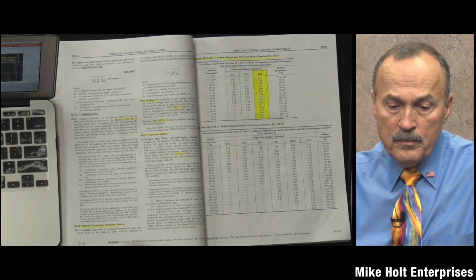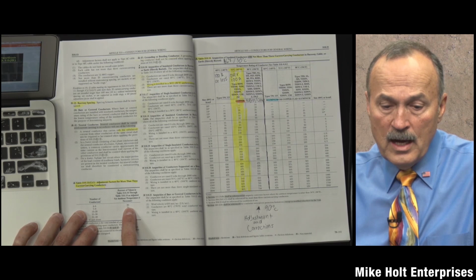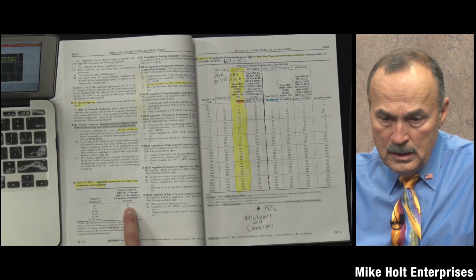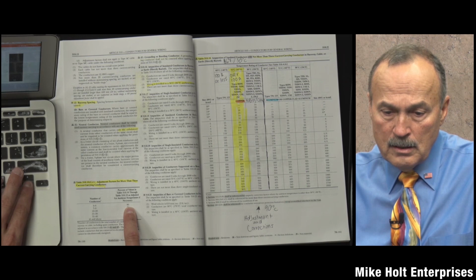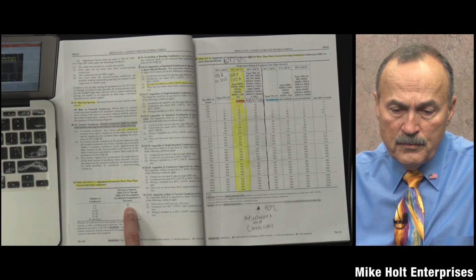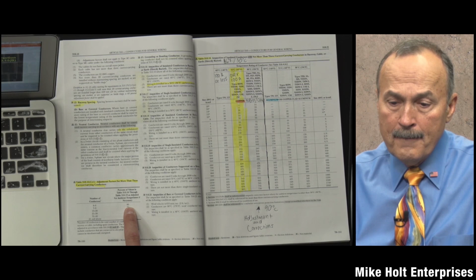And then if I go to the 310.15(C)(1) table, for five current carrying conductors, 80%. Well, I'm missing the answer here. Am I not missing the answer? Oh, no, it's right there. I'm sorry, I missed it. The red threw me off here. 115 amp at 90 degrees C, corrected for the temperature, adjusted for the bundling, comes out there. This is an 80 amp wire along its entire length, right?